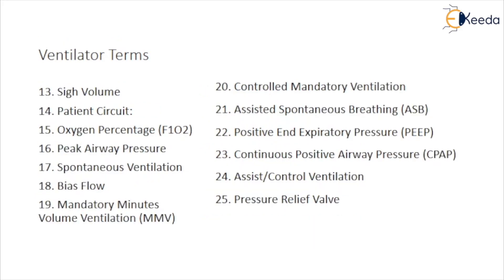Peak airway pressure is the highest level of pressure reached over several breaths. Spontaneous ventilation is a mode in which the patient initiates and takes breaths from the ventilator at will. In the bias flow, mixed gas from the mixers is redirected through the patient circuit between mechanical breaths, stabilizing baseline pressure. Sensitivity is used to detect spontaneous effort by the patient in order to trigger mandatory ventilation with a set respiration rate.